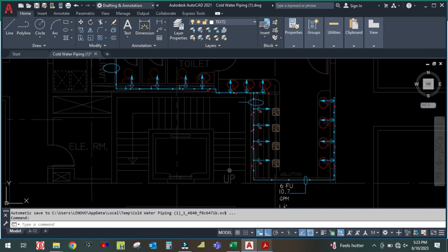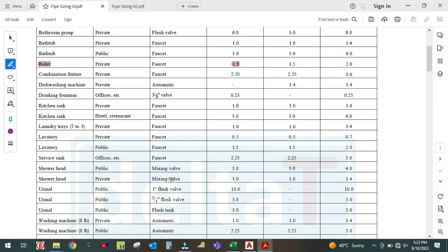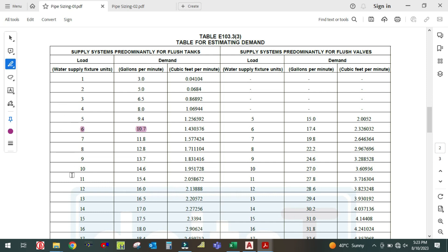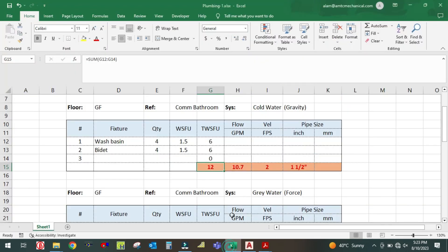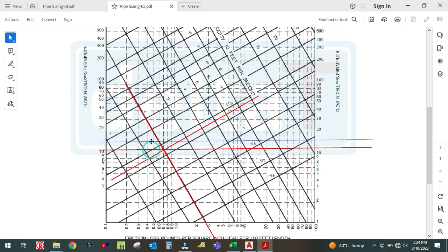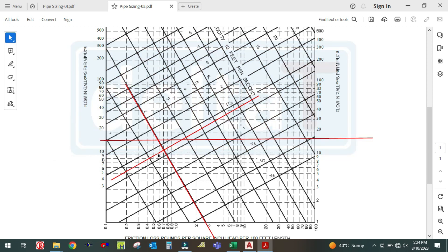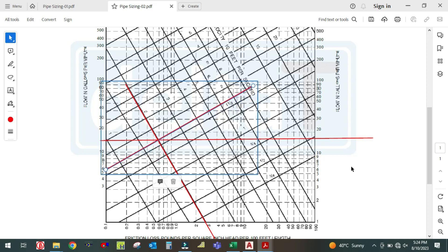For 12 fixture units, the GPM is 16 GPM. Check the pipe size in the chart: 16 GPM plotted against the velocity line again comes out at the same one and a half inch pipe size.